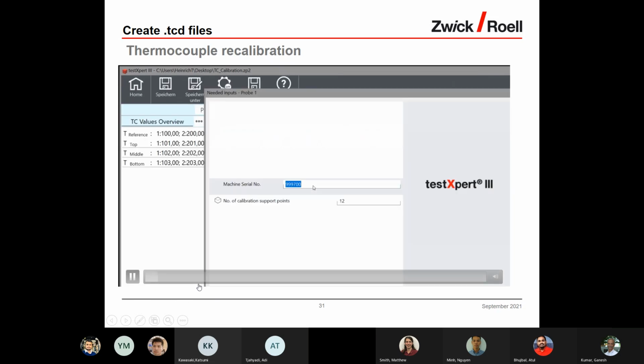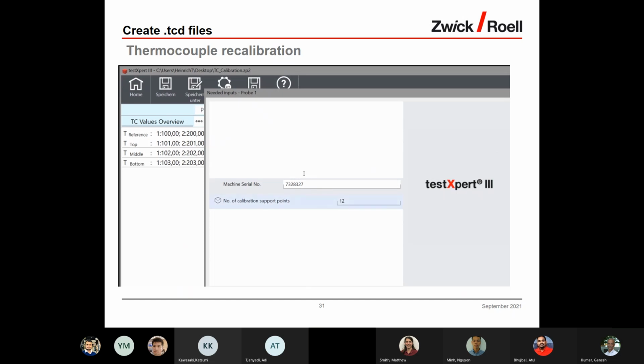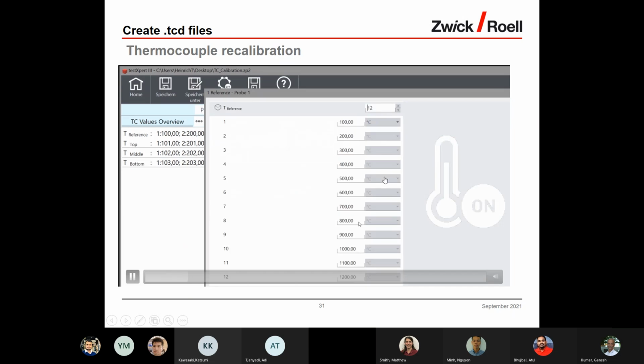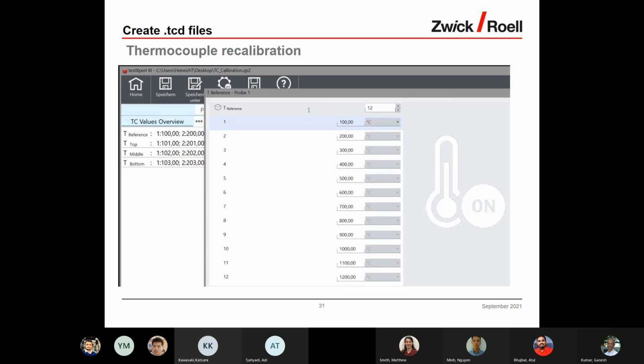Here we have a test specification so that we can create the .tcd files with the external calibration values. First open the test specification and then enter the serial number of the machine. We have 12 support points to enter. This is now the temperature of the reference.